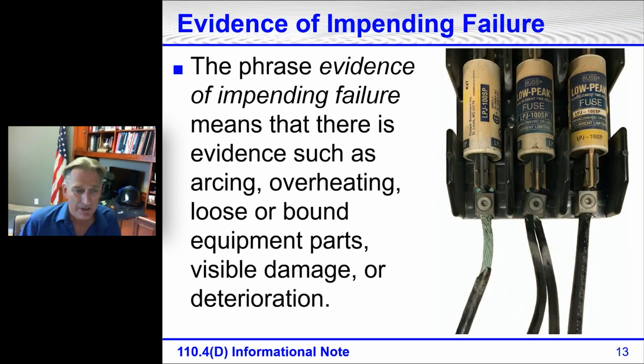This last item here, the phrase evidence of impending failure means that there is evidence such as arcing, overheating, loose or bound equipment parts, visible damage, or deterioration. I was teaching in Lansing, Michigan a few years ago, and they showed me this fuse block that came out of a piece of equipment. I'm not sure exactly what it came out of, but looking at that, is there evidence of impending failure with that fuse block? The top conductors were just as bad as the lower ones here. And the answer, of course, is yes. There is evidence of impending failure.